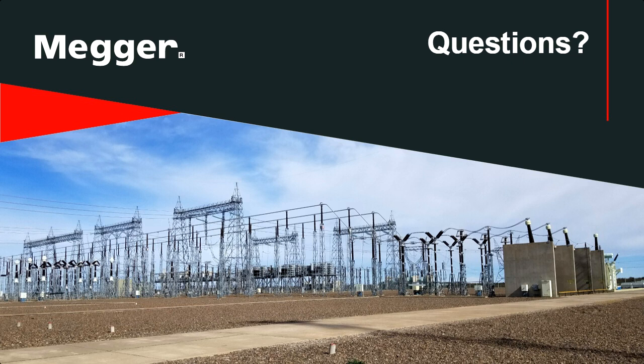As far as your IR test, that's your insulation resistance test, or what's commonly known as the Megger test. And all you're doing on that is... most people don't really utilize that test on your higher voltage breakers. That's usually on your lower voltage breakers. They typically do this, but it's still a fine test to do on your higher voltage EHV breakers, where you'll do your line to load, and you'll look at it with an open, right? And then you also look at, while it's closed, your phase to phase, and then your phases to ground. And you want to make sure that there is a high ohmic value, usually in the gigs.